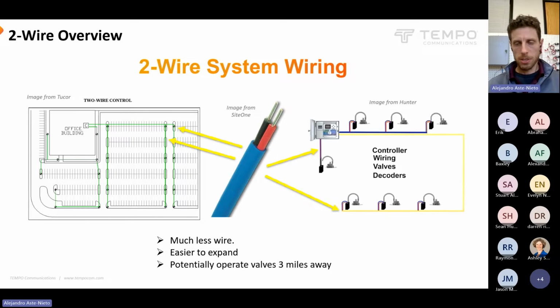These systems tend to start to make more financial sense when we have a lot more valves to operate, because you're saving that much on wire. But on smaller systems, it doesn't always make financial sense, because decoders are not negligibly costly. They tend to be at least $100 each retail or so. So right when you get to maybe 30 or 40 valves or more, it starts to break even and then be cheaper when you're using less wiring on a 2-wire system. Obviously, there are other benefits in terms of simplicity, the ability to do diagnostics, and being easier to install with fewer wires going in, but those are the main benefits.